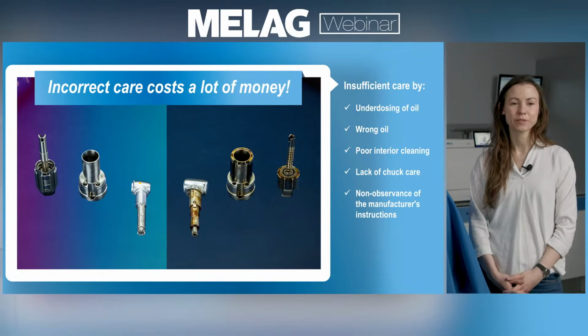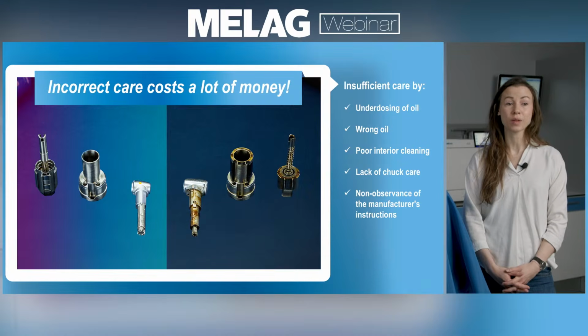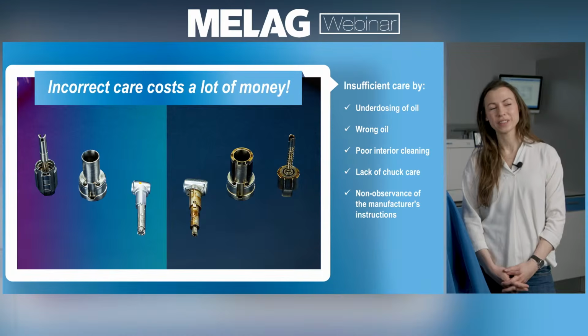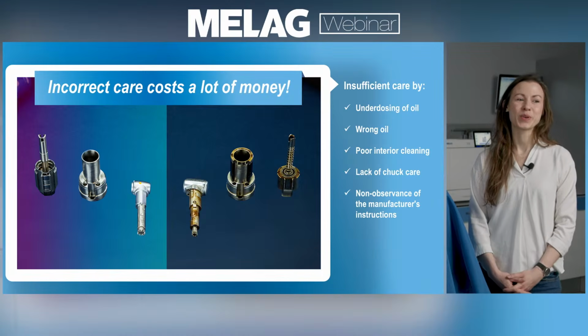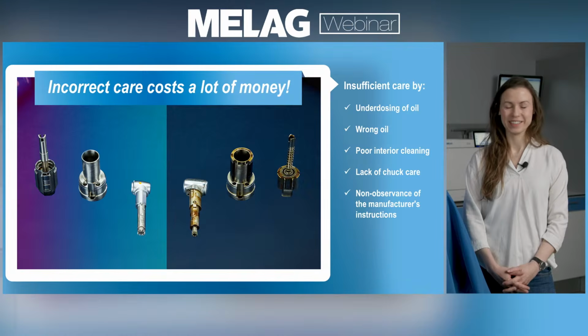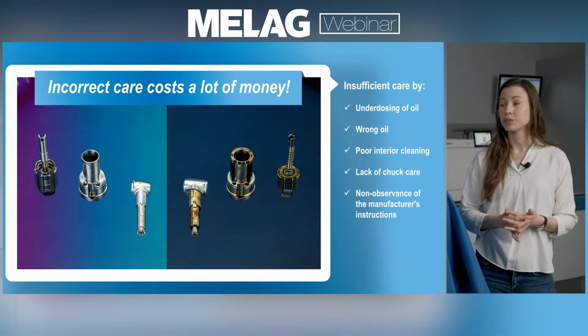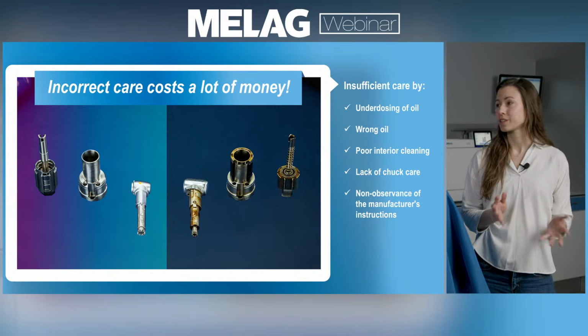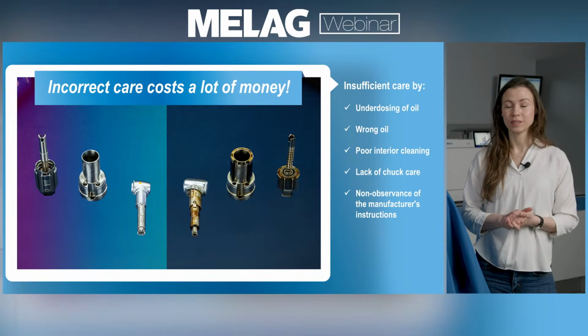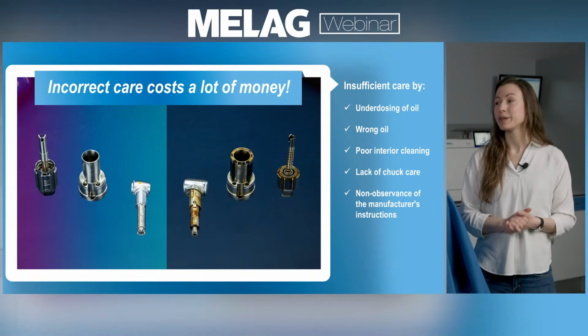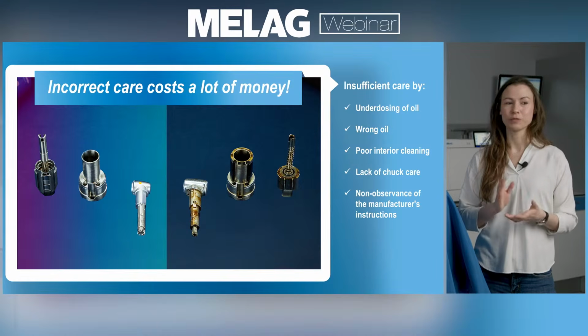You can see here on the left-hand side how well-maintained instruments should look. On the right-hand side you see the other end of the spectrum. What are the reasons it looks like this? One reason could be that you underdose the oil of the instruments. There's no such thing as over-oiling instruments. They need to be oiled really well from the inside to make sure everything is nicely lubricated, especially with high rotation speeds. We're talking about 200,000 rotations per minute. That's very fast. Yeah, very fast. Therefore, you need to make sure the inside components can move really smoothly.